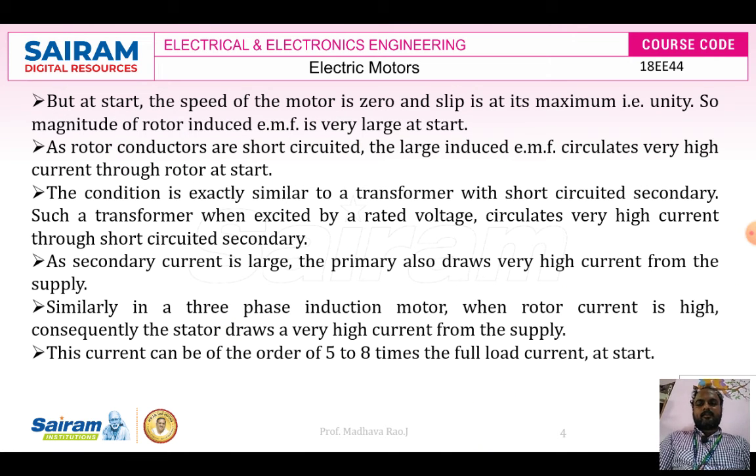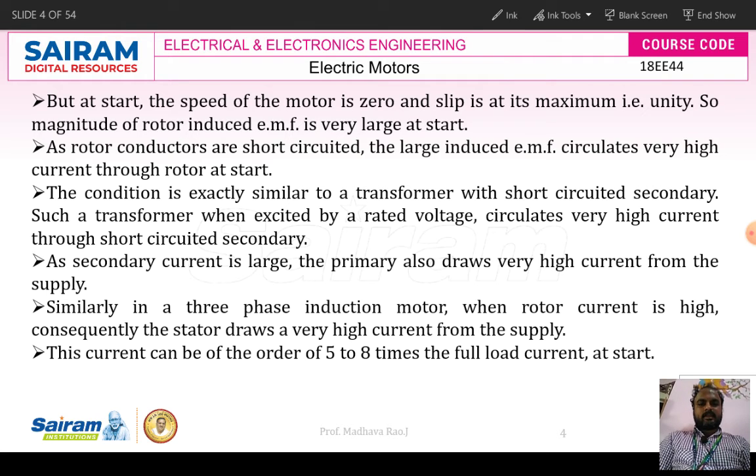Already we have seen that at start the speed of the motor is 0 and slip is maximum. So NR, the rotor speed, is equal to 0, and S is equal to (NS minus NR) by NS, so slip is maximum, that is unity. The magnitude of the rotor induced EMF is very large at starting. Rotor conductors are short circuited, and the large induced EMF circulates a very high current through the rotor circuit.